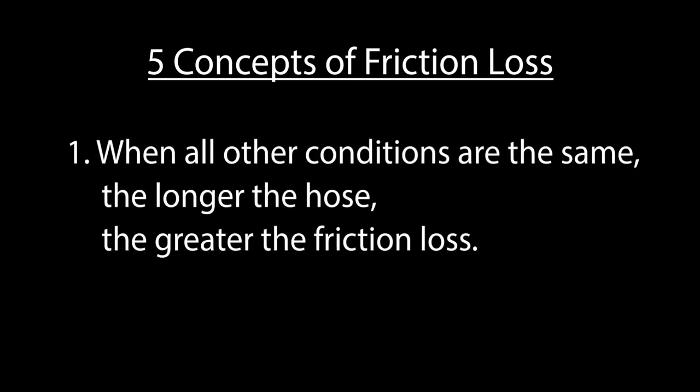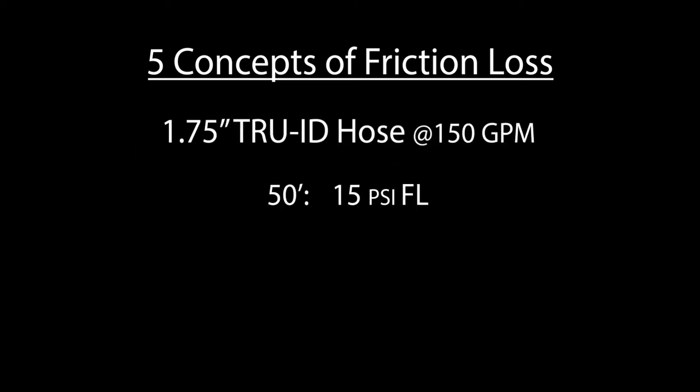There are five fundamental concepts that every engine operator must understand when it comes to friction loss. First is that when all other conditions are the same, the longer the hose, the greater the friction loss. This simply means that the more hose that water must move through, the more friction loss it will encounter.